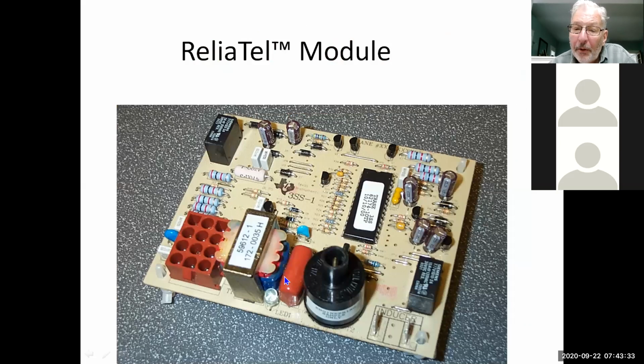We have 2 different boards for these units. There's a ReliaTel board and electromechanical board. So the ReliaTel board talks to the RTRM. The electromechanical is kind of standalone, and those are the only 2 different boards that we stock for these rooftops. Okay, and again, you're going to see on these boards, you'll see high and low inducer taps, and if it's a single stage unit, it's only going to use one of the taps on there. So boards are interchangeable from 1 and 2 stage, but not between ReliaTel and electromechanical.